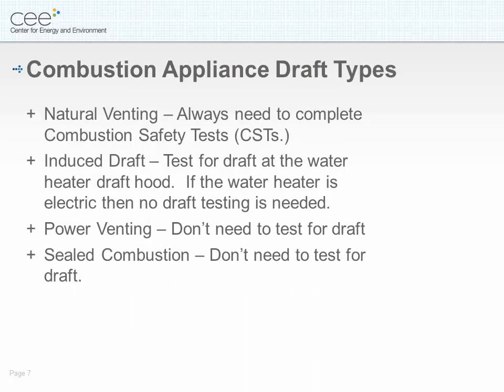Combustion appliance draft types. Natural venting: always need to complete combustion safety tests. Induced draft: test for draft at the water heater draft hood. If the water heater is electric, then no draft testing is needed. Power venting: you do not need to test for draft. Sealed combustion: you do not need to test for draft.